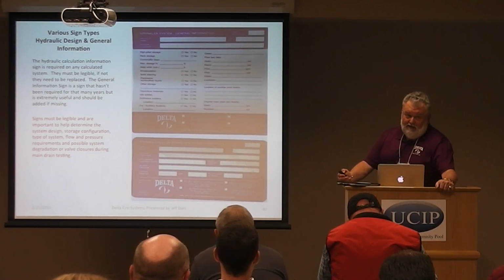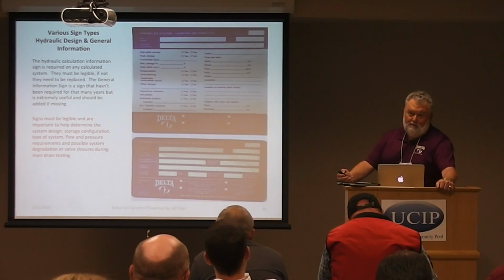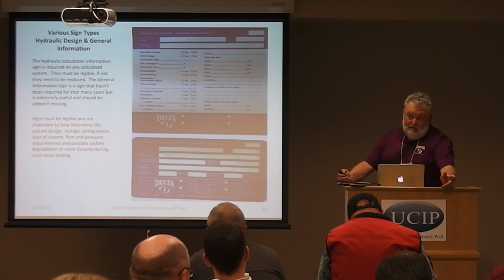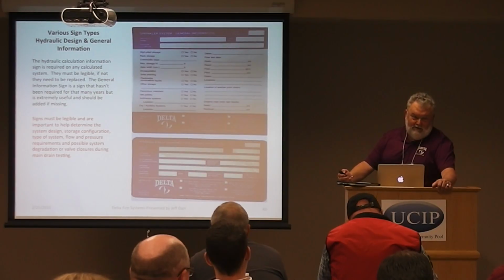The hydraulic signs tell you exactly what the system was designed at, the pressure at the base of the riser. When you do an inspection and the hydraulic sign says you had to have 60 pounds at the base of the riser and you only have 30 pounds on your gauge, right away you know you have some potential problems.